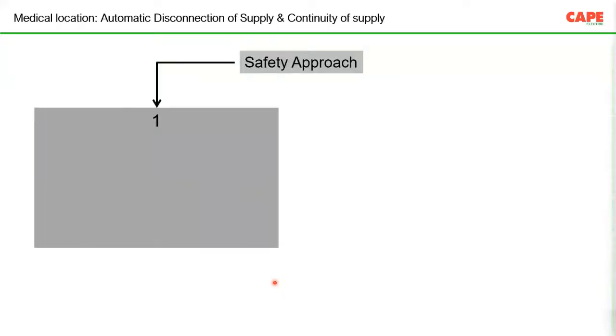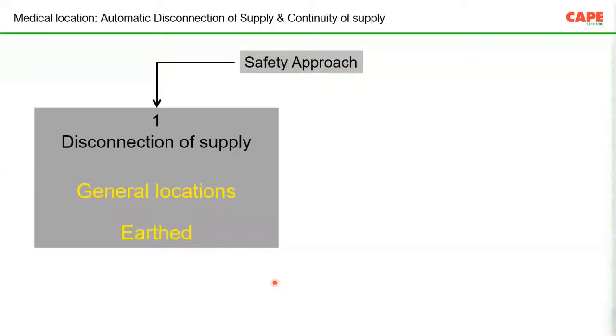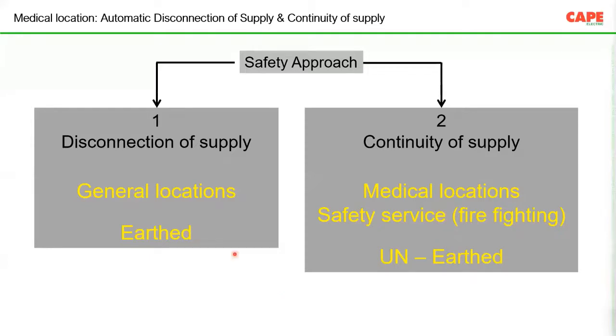We always have a confusion. What exactly is the TN system or TT system? Because for safety, the first point is what kind of system earthing you are doing. Now, with respect to safety, system earthings are classified into two. The first one on the left side is an electrical installation where safety is achieved by disconnection of supply. Disconnection of supply means in case of any fault, the supply must be disconnected within a certain time, before the touch voltage is harmful to a human being. This is safety measure number 1. It can be used in general locations, and this is also called the earthed power supply.